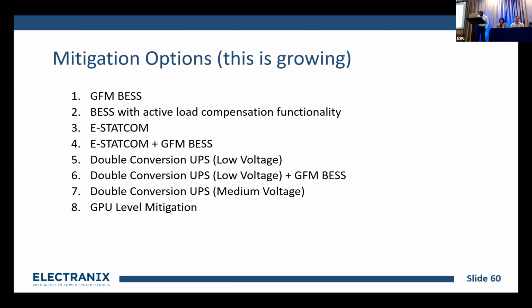And then we have three double conversion UPS type mitigation methods. One is the low voltage one, which is the industry established method for typical UPSs, the online double conversion UPS. The second one is the same online double conversion UPS with a GFM battery, because these low voltage double conversion UPSs are again a low energy mitigation method, so you need some kind of supplementary power. And the seventh one is the medium voltage double conversion UPS, which inherently has a large energy storage, so you don't need a separate battery or energy storage on top of that. And the last one is the GPU level mitigation. Scott is probably going to talk about it, hopefully. I don't know much about that.